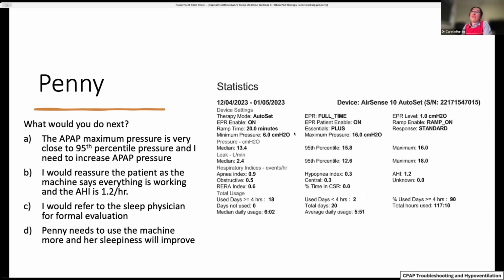The other thing this machine can also tell us is how much leak the patient's having. And this, in fact, says most of the time the median leak is 2.4 liters per minute, which is actually quite good. And 95% of the time, the leak is 12.6 liters per minute or less. And generally speaking, we would consider a leak of less than 24 liters per minute as being a reasonable mask fit. So here are your choices. What would you do next?